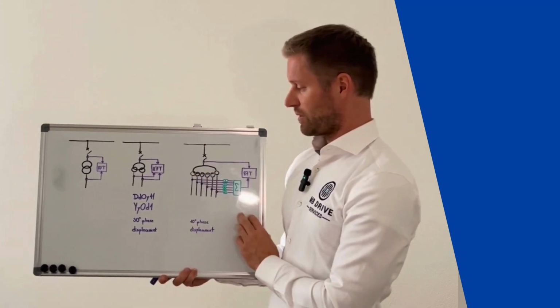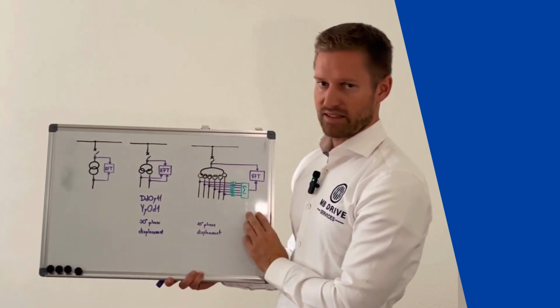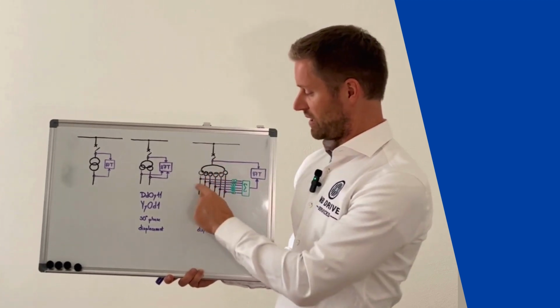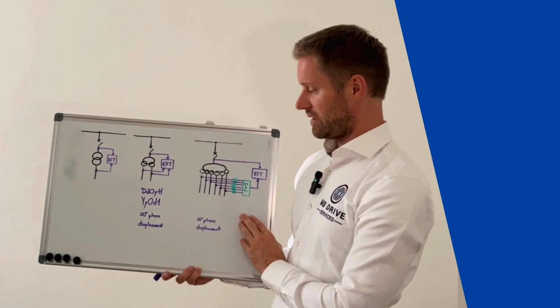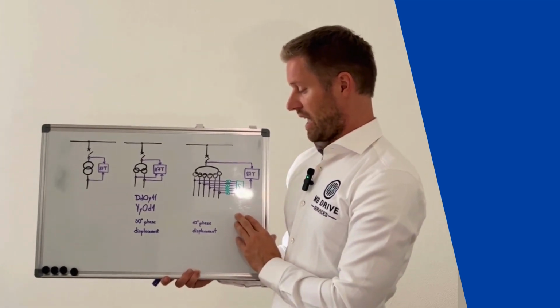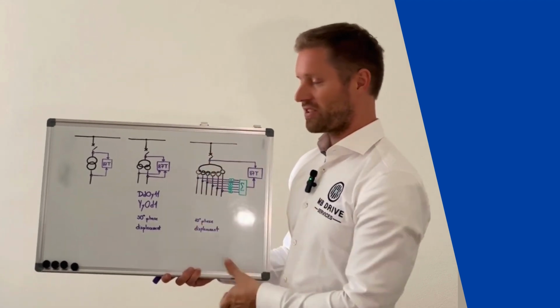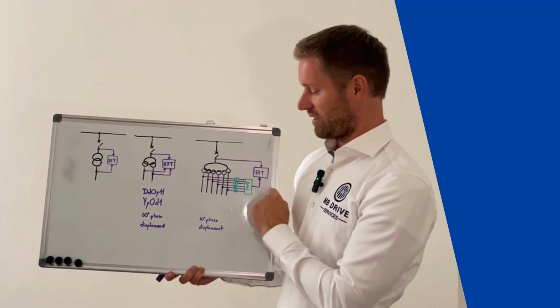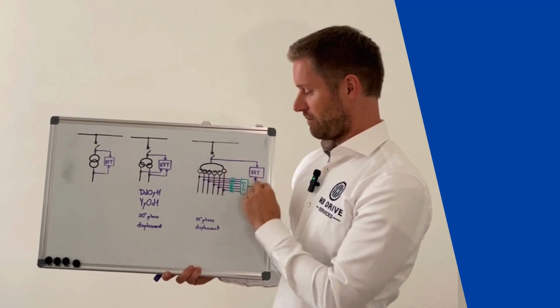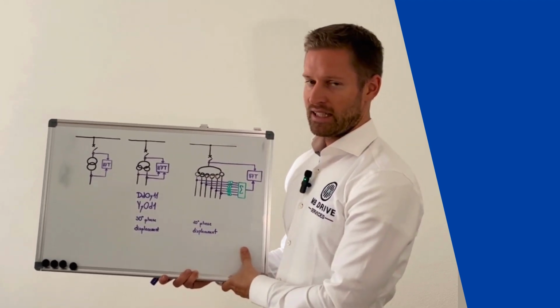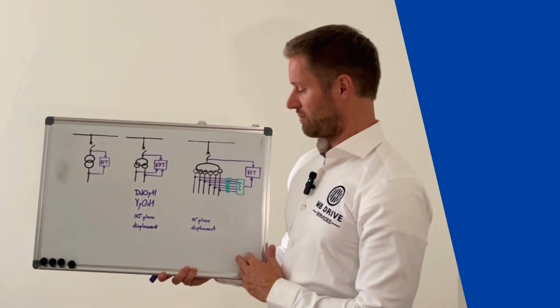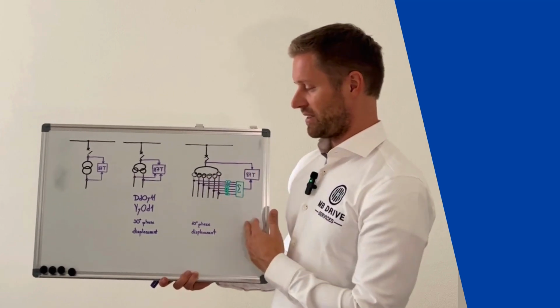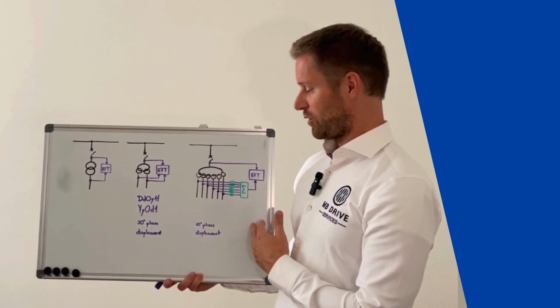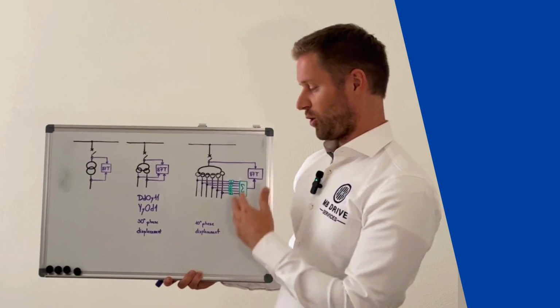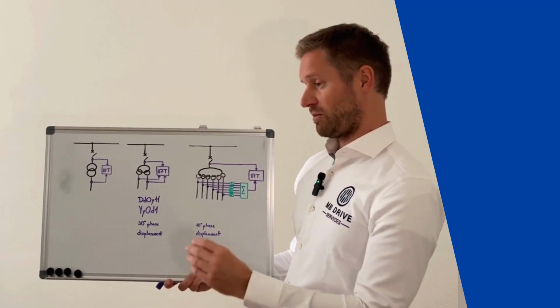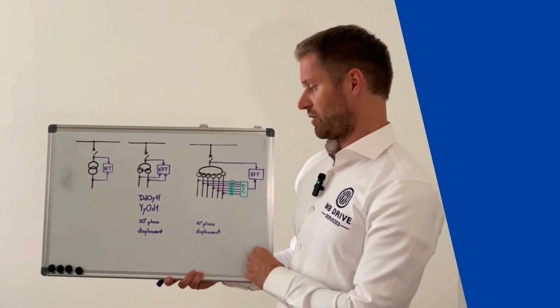For a multi-winding transformer, so more than 3 windings, higher complexity, I would be definitely more careful. We see here that the number of components involved is increasing significantly, and also the whole protection scheme needs to be engineered, because it's not supported by the relay itself. We need to do some work around, some engineering around. This is also a possible risk of wrong implementation. So either there could be some faults which are not real, where the relay should not trigger, or on the other hand, the sensitivity would be much lower than expected. So one shall be careful.